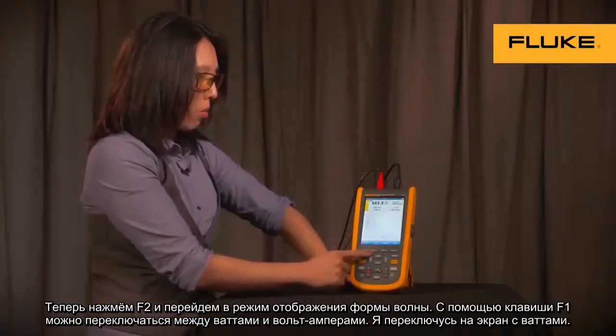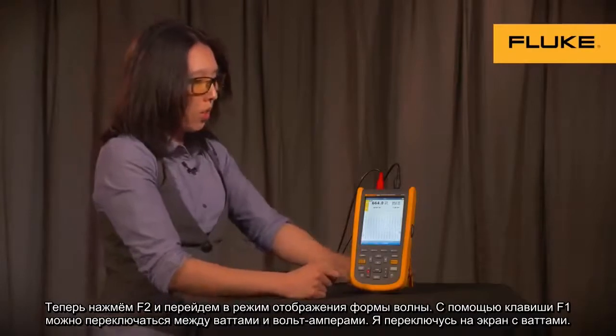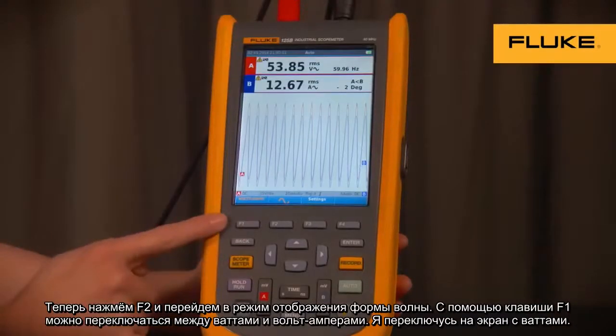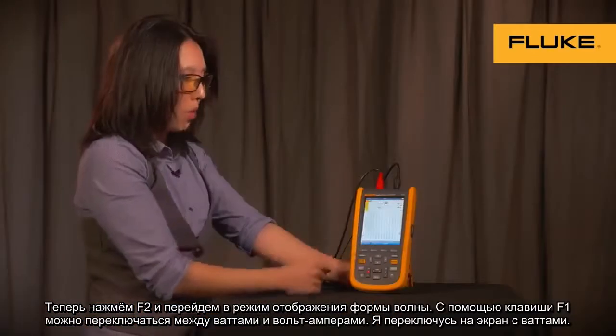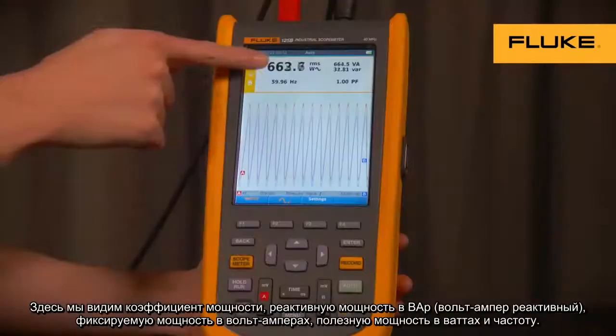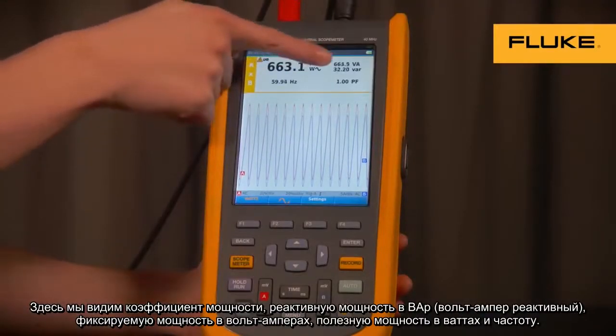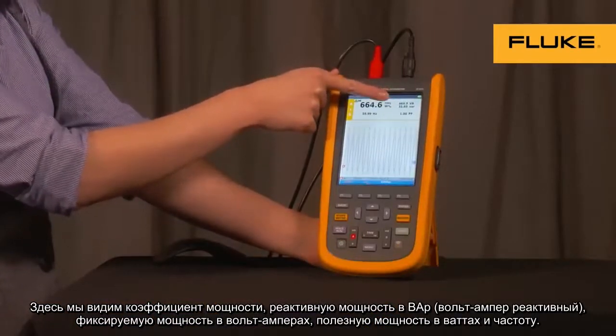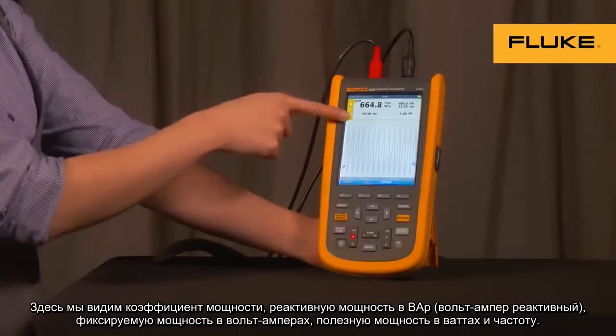Now let's toggle to the waveform by pressing F2. You may choose watts or volts/amps by toggling F1. Let's toggle back to watts. Here you can see your power factor, your reactive power in VARs (volt amps reactive), your apparent power in volt amps, your real power in watts, as well as frequency.